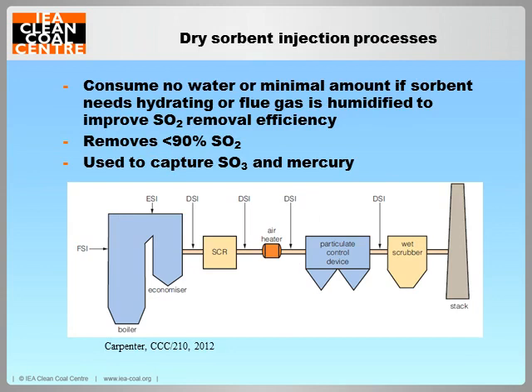However, sorbent injection systems are best suited to small or medium-sized power plants which are burning low to medium sulphur coals and where only a moderate sulphur dioxide removal efficiency is required. The sulphur removal efficiency is lower than for wet and semi-dry scrubbers. The dry sorbent injection processes are being used to control sulphur trioxide and mercury pollutants by using just a suitable sorbent.